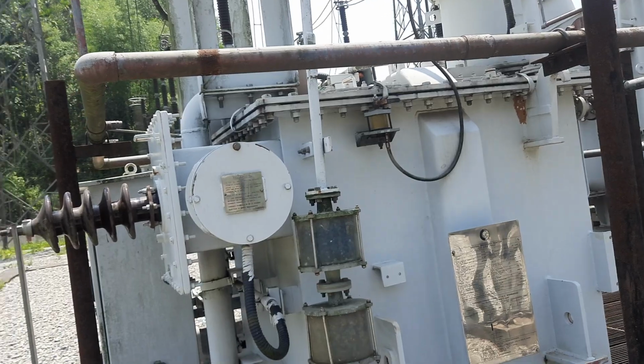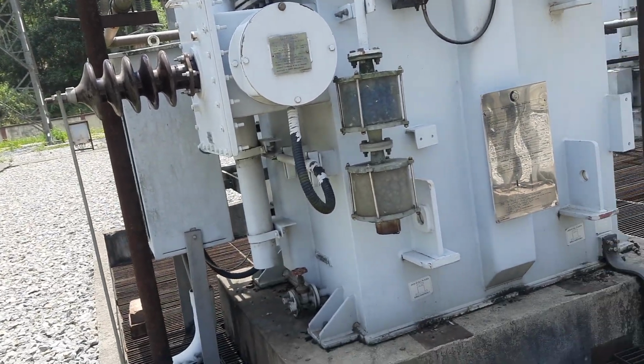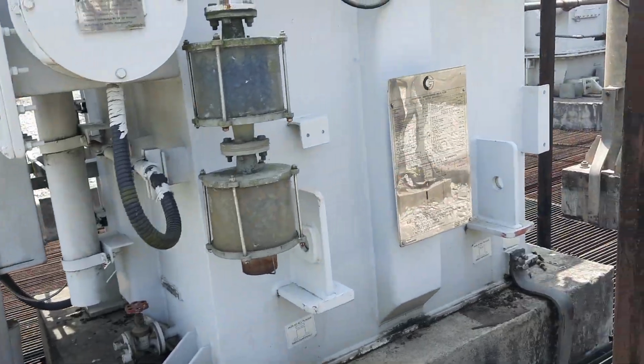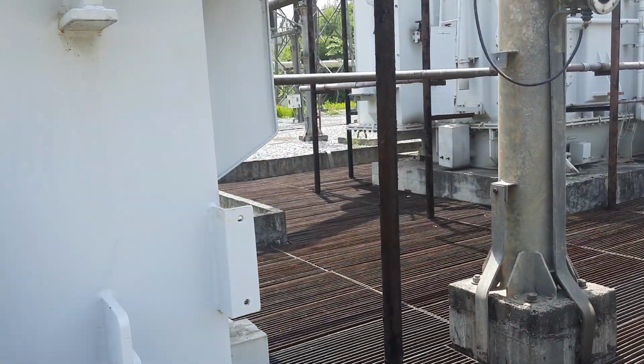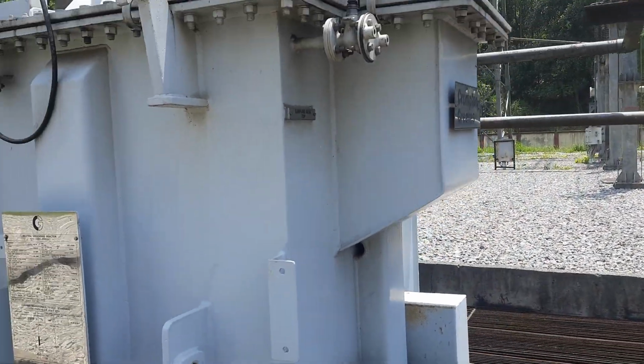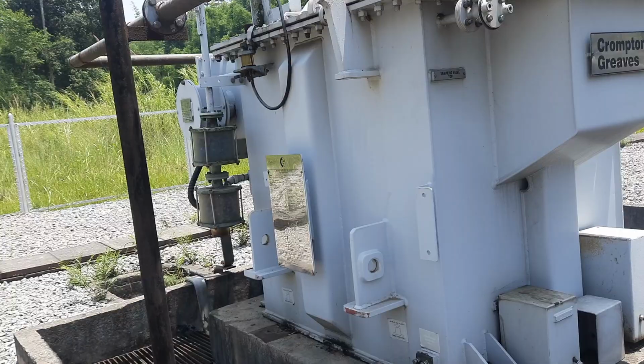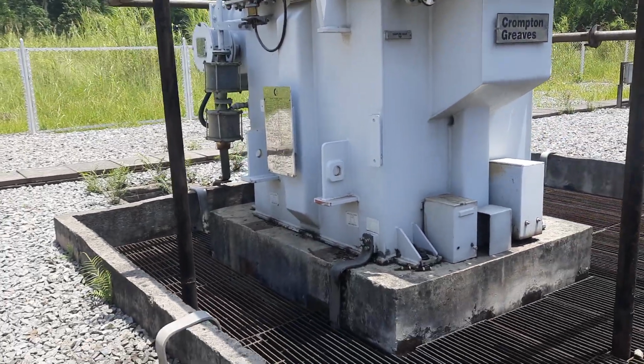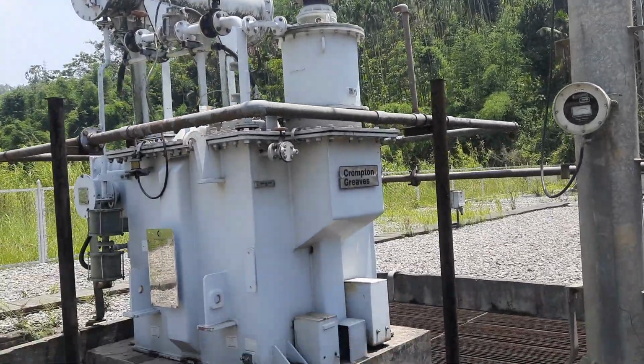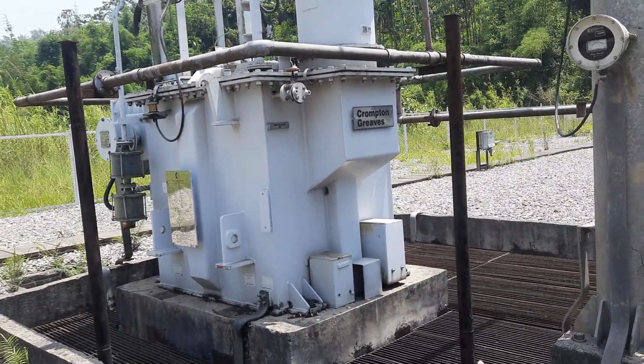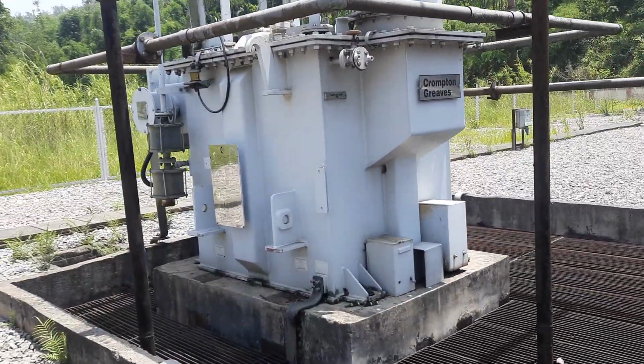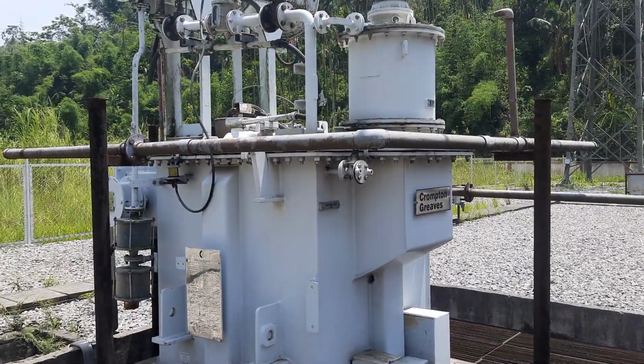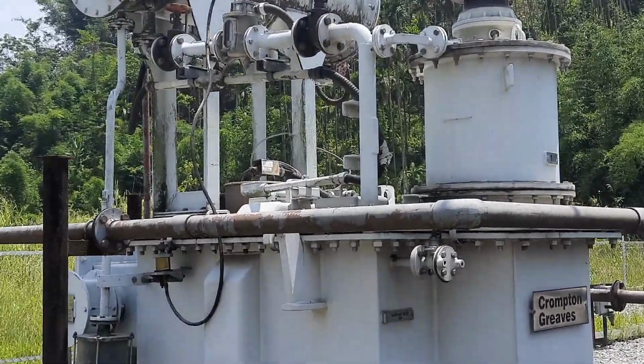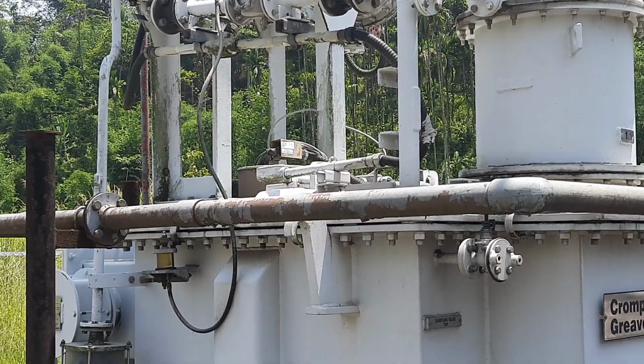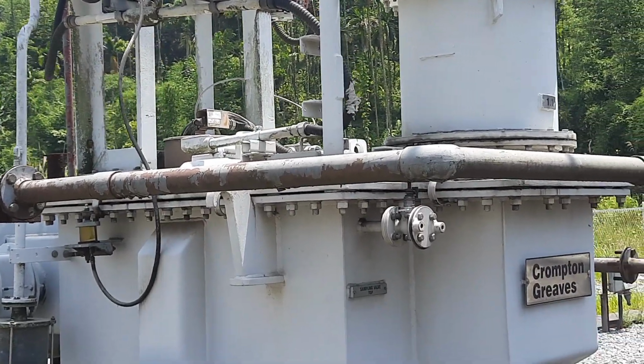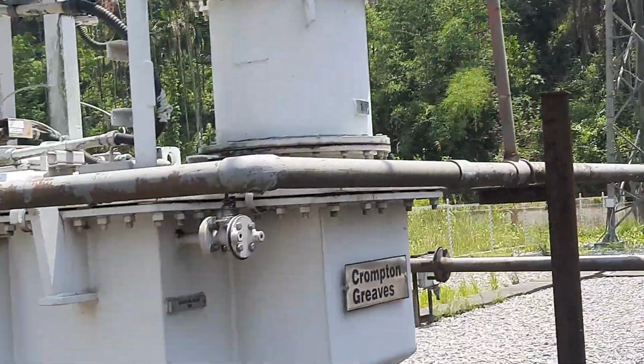The cooling system of this is oil natural, air natural, that we call ONAN. That's why we are not installing any fan or pump for this NGR, because normally it is not loaded much; in an ideal system it has no function, and we are providing it just for protection purposes. So the oil will flow by itself. Even the PRV, the pressure relief valve, you can see on top has also been provided, and its function is the same as in a transformer, with one bushing and so on.